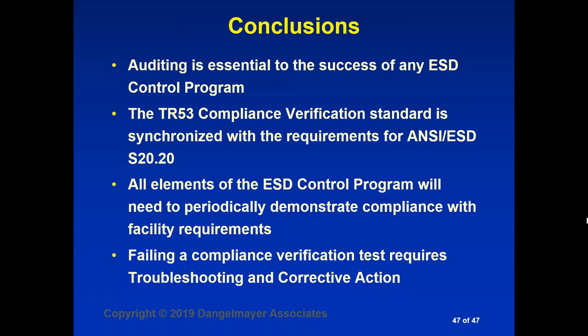Failing a compliance verification test requires troubleshooting. It requires corrective action. The troubleshooting part of it is actually contained in TR53. In our longer auditor certification course, you will get all that troubleshooting information, but it almost always also requires corrective action of some kind. Troubleshooting may be in the auditor's job description. Corrective action is probably not. Someone else will have to correct the problems. The auditor's job will be basically to flag the problem and make sure that something is going to be done about it, and also to make sure that the area where the compliance verification test failed is adequately marked so people don't continue working in that area until the corrective action has been taken.